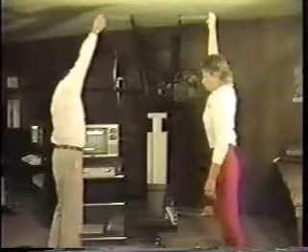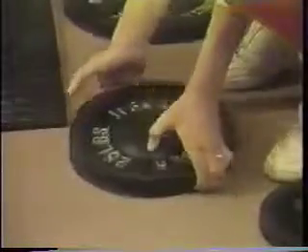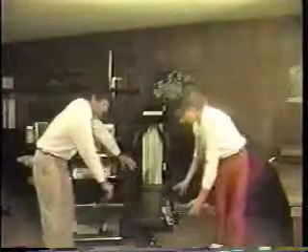Move the bar to stop position, move the bar to start position, and we hang 50 pounds of weight on the bar. That's it. Put it on the bar. Back up, please. Release. Thank you. Again, that was for velocity calibration. We'll now demonstrate position calibration.